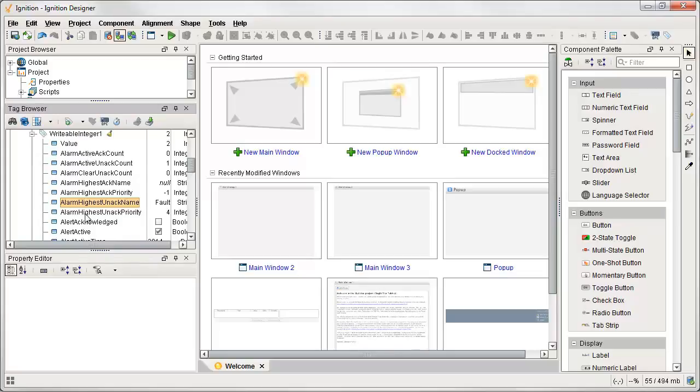And so there are quite a few meta properties that we can actually use on screens. I can just drag these onto a screen and display them in labels or buttons or circles or whatever I want to display them. So if I set this value here to a value of 1, that would actually clear the alarm. And so it would no longer be active. As you can see, alert active is false. If I set it back to 2, it's going to be active again. You can see it go to true. So it's very easy to configure simple alarms on tags.